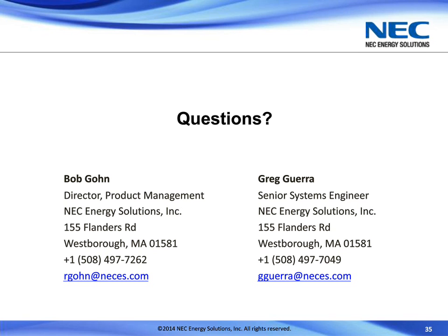Swiftly moving on, our next question is, any flammable off-gassing? And the answer to that is no. Unlike some of the lead-acid batteries that, particularly when they're being stressed at high charging and discharging rates, can off-gas dangerous gases and release them, particularly the flooded batteries, to the extent that for large installations they really need to be kept in separated battery rooms for safety's sake. There is no flammable off-gassing. So this allows the lithium-ion batteries to actually be used in some environments where lead-acid might be inappropriate, or special containers might be required to vent the battery room to prevent any buildup of such gases.